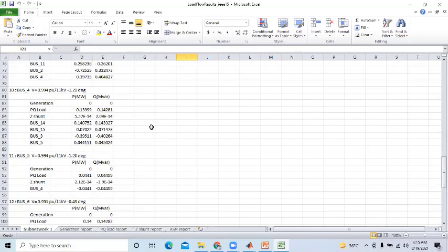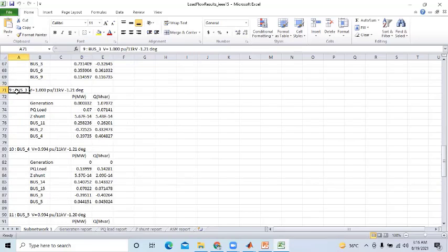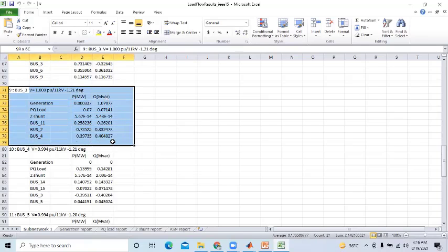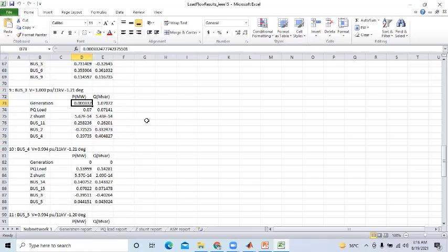Look at this. This is the bus number. If you look at bus number 3, we know that we have connected one DC generator at bus number 3, which is generating 0.332 kilowatt of real power, and it is generating 1.070 MVAR of reactive power. A load is also connected over here, and it is supplying the load to bus number 11. The power flowing from bus 3 to 2 is this much, and bus 3 to 4 is this much.